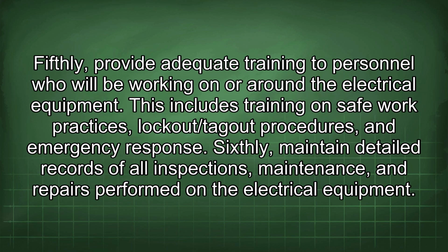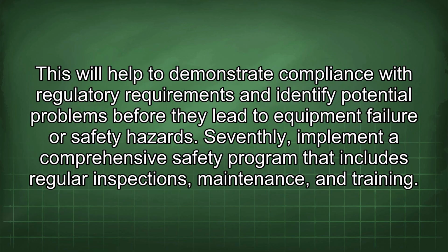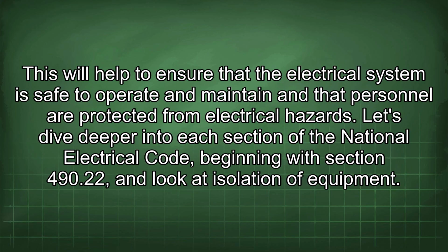Fourthly, install proper guarding and isolation devices to prevent unauthorized access and protect personnel from accidental contact with energized parts. Fifthly, provide adequate training to personnel who will be working on or around the electrical equipment. This includes training on safe work practices, lockout/tagout procedures, and emergency response. Sixthly, maintain detailed records of all inspections, maintenance, and repairs performed on the electrical equipment. This will help to demonstrate compliance with regulatory requirements and identify potential problems before they lead to equipment failure or safety hazards. Seventhly, implement a comprehensive safety program that includes regular inspections, maintenance, and training. This will help to ensure that the electrical system is safe to operate and maintain and that personnel are protected from electrical hazards.